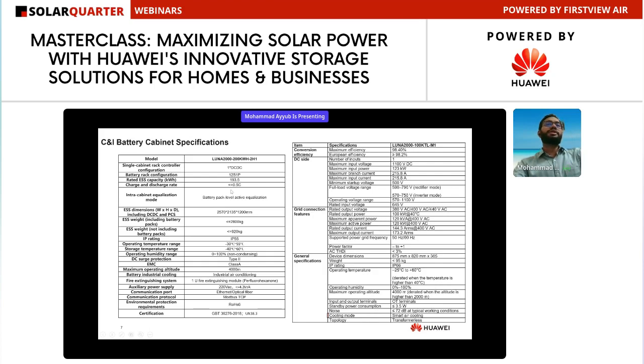This product supports a C rate of 0.5C or less. Our product power capacity is 100 kilowatt and energy capacity is 200 kilowatt hour, so it supports up to a maximum 2 hour backup. It has a weight of less than 2.8 tons, including battery packs and everything inside the system, and the IP rating is around IP55. So this is a perfectly outdoor system, we can put it outside in the environment as well, it's not an issue. These are the specifications for the battery system.